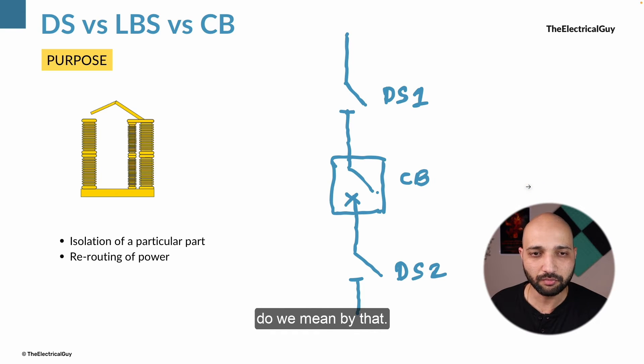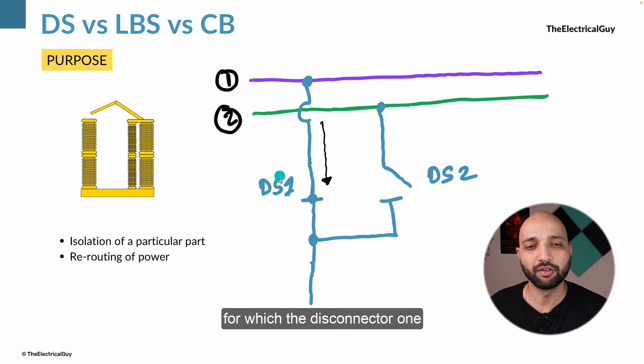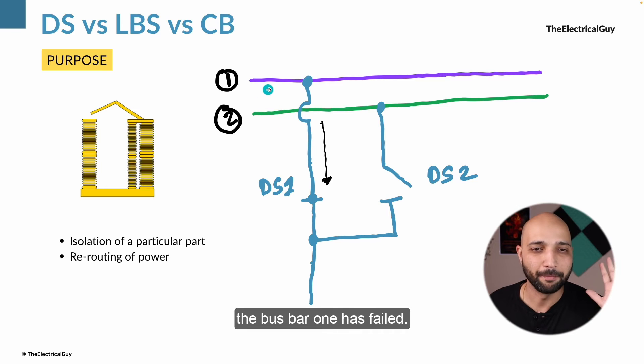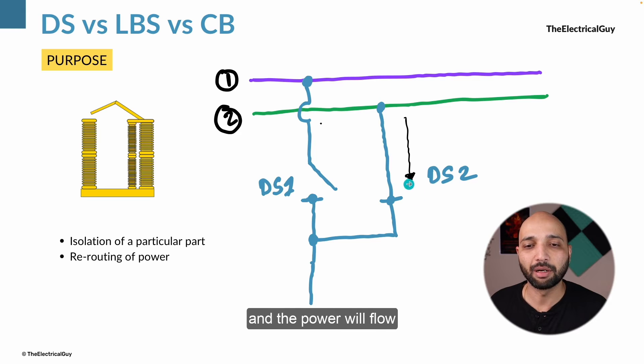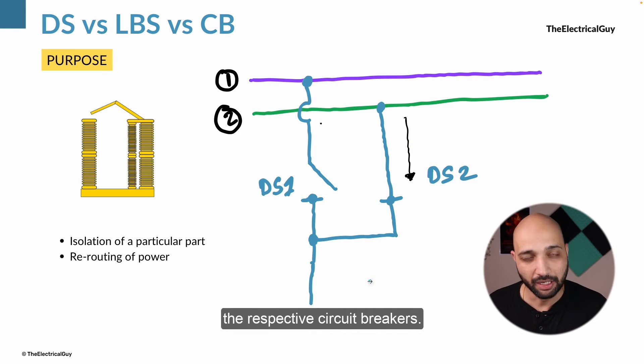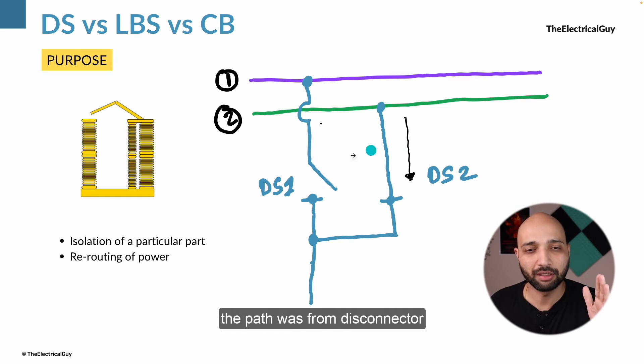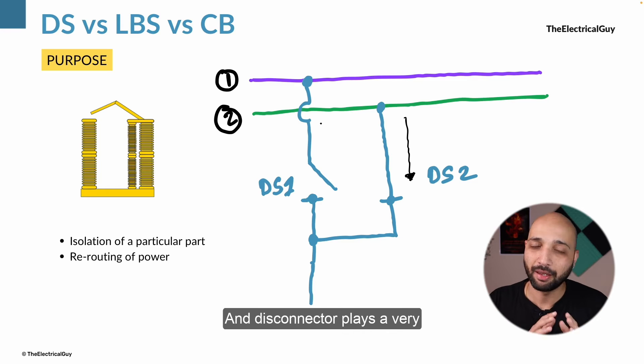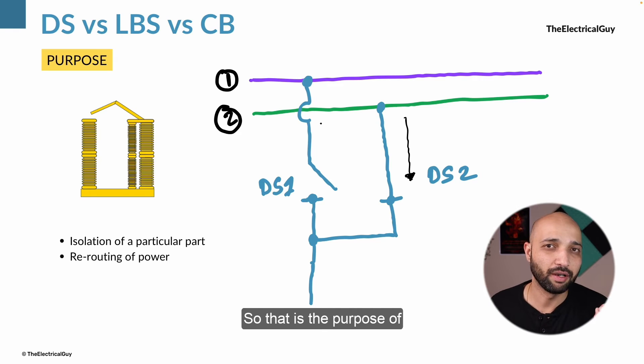The second purpose of disconnectors is rerouting of power. For example, with two busbars — busbar 1 and busbar 2 — if busbar 1 fails, I can open disconnector 1 and close disconnector 2 to reroute the power via busbar 2. This of course happens after opening the respective circuit breakers. Disconnectors play a very important role in substations for this purpose.